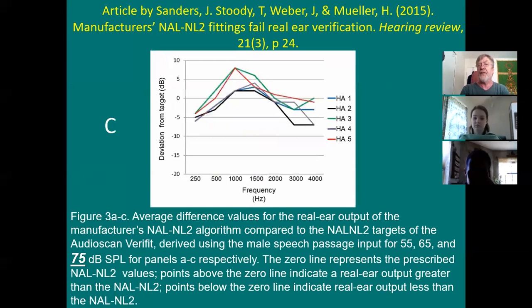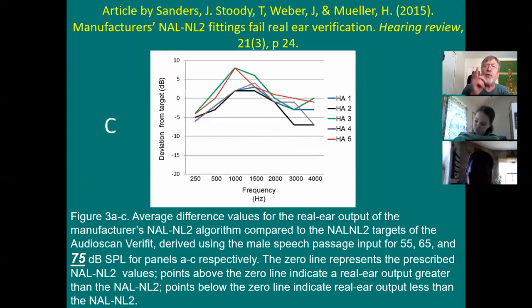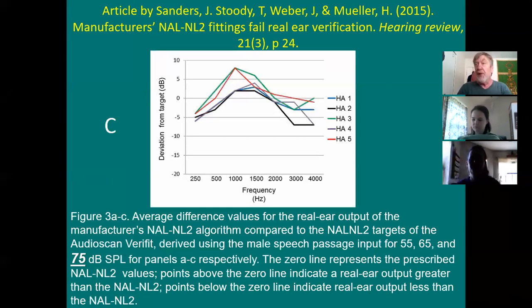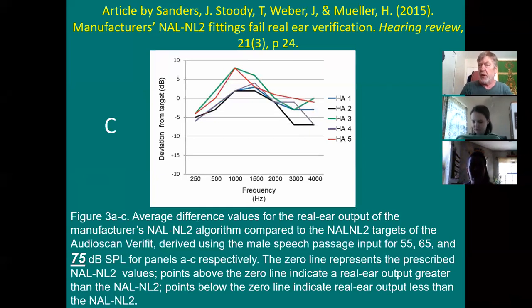For 75 dB inputs, many manufacturers' NAL-2s are asking for more output than the NAL-2 on the real ear equipment — but again, less in the highs. It's all weird, it's all strange. Not only are manufacturers' proprietary methods asking for less output than most fitting methods, but when they use NAL-2, they all use it differently. And that's why real ear cuts it — real ear is what shows what you really want.